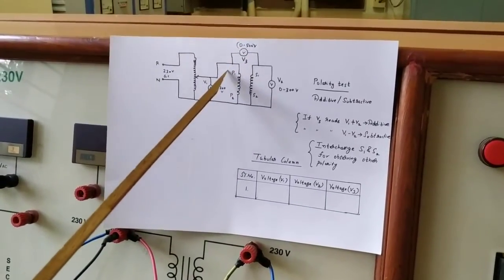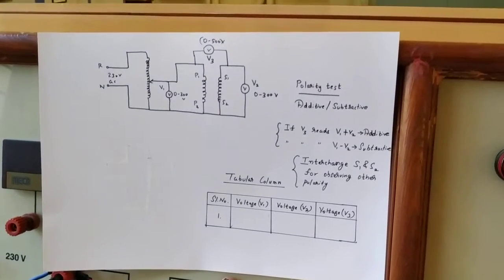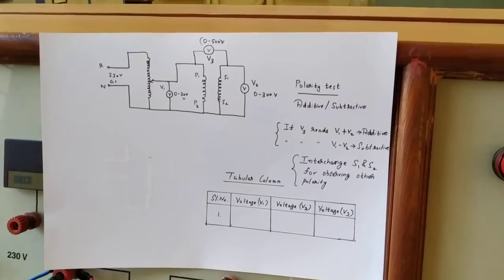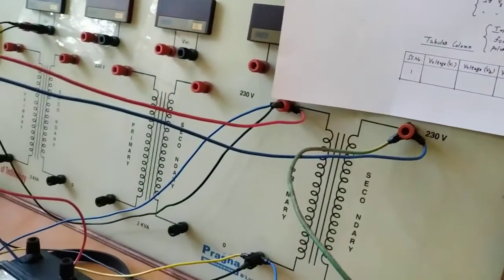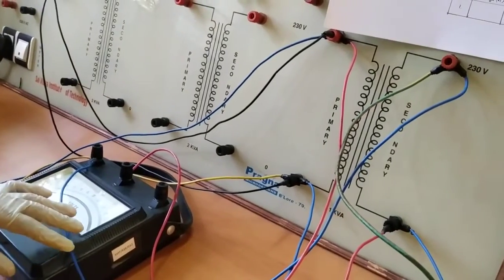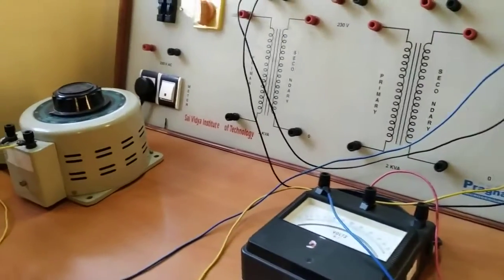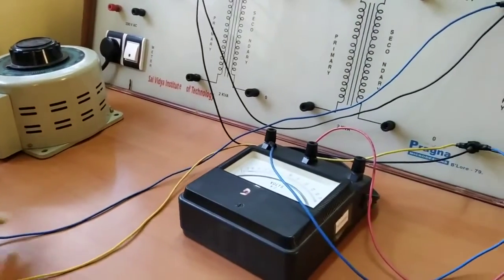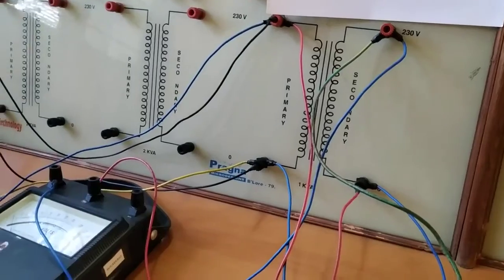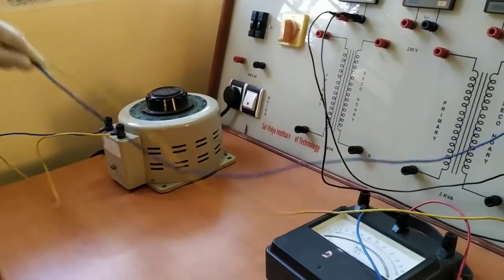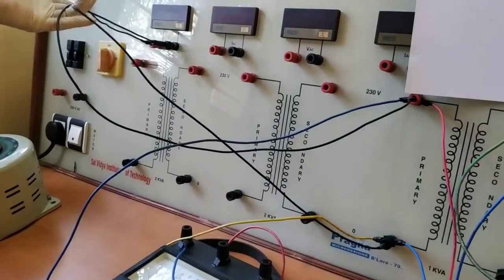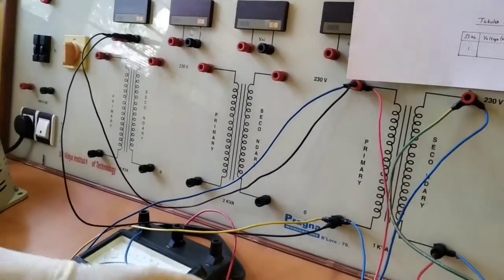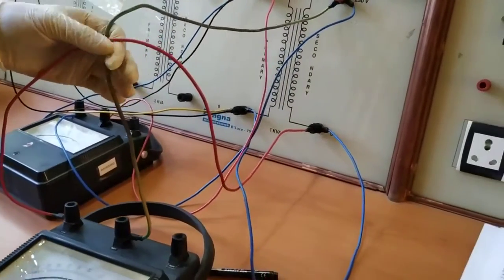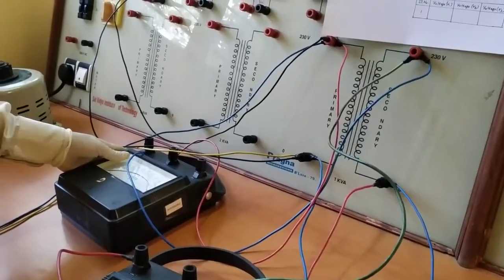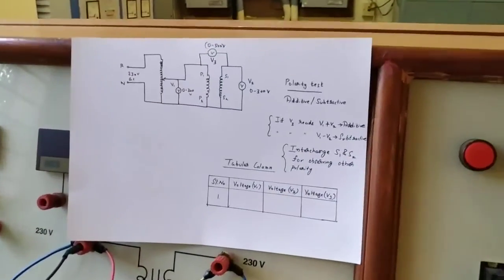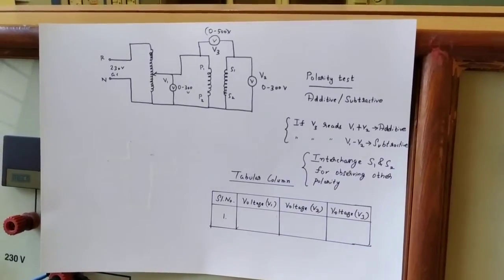Voltmeter V3 is connected between P1 and S1. So this shows the connectivity. To summarize the connectivity, first it starts from the auto transformer. From the auto transformer, it is connected to P1. Then P2 is coming back to the auto transformer. We have a voltmeter connected across P1 and P2. Then across the secondary, we have another voltmeter V2. Then we have another voltmeter V3 between P1 and S1. So this is the circuit connection configuration. Next we'll go for the working.